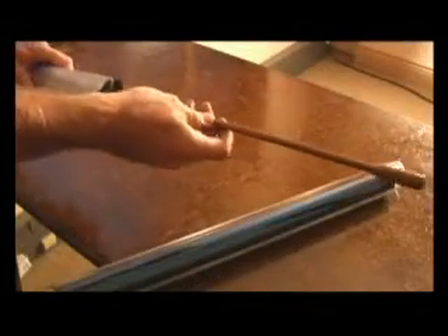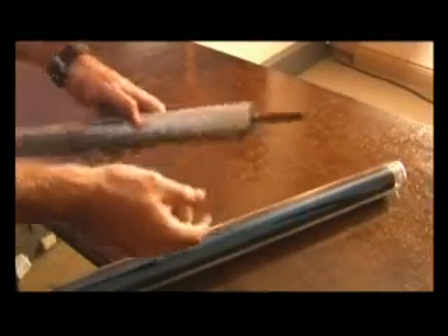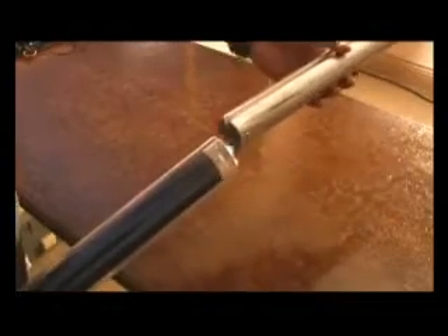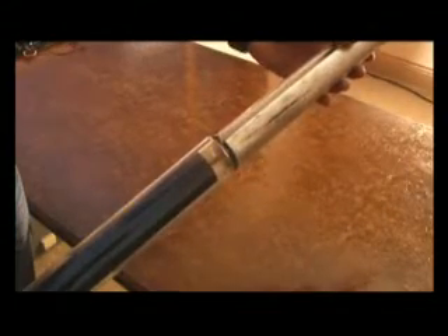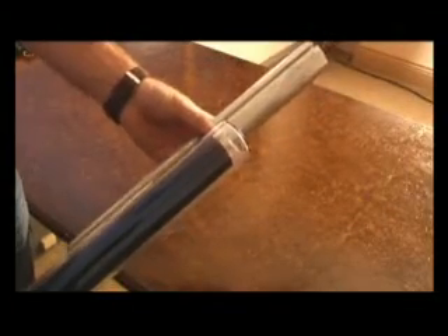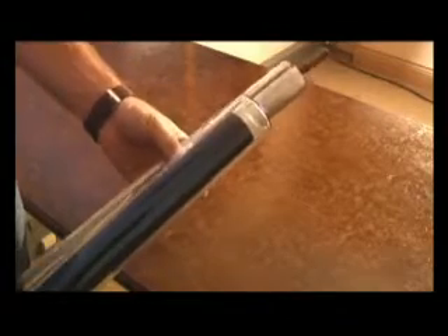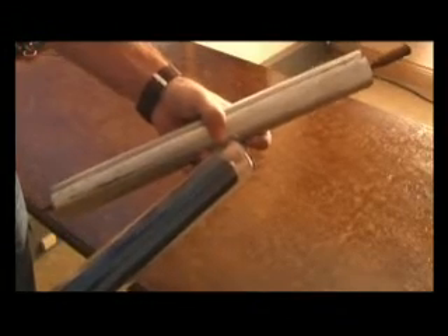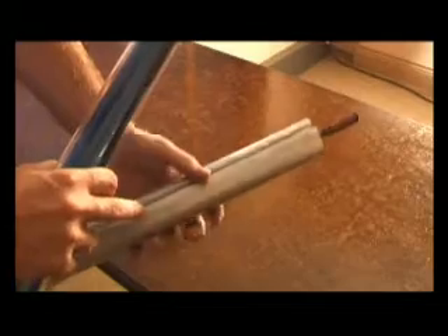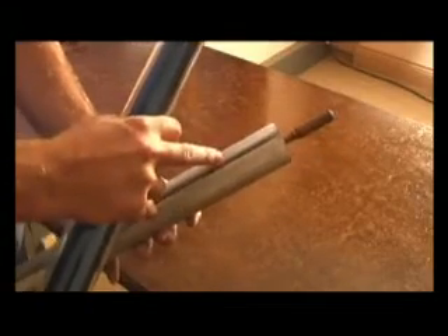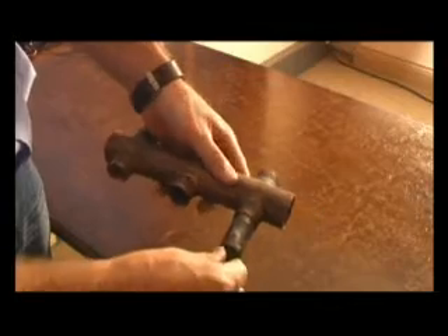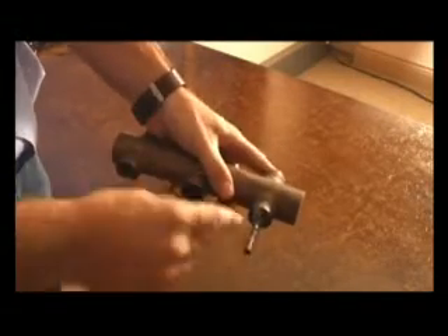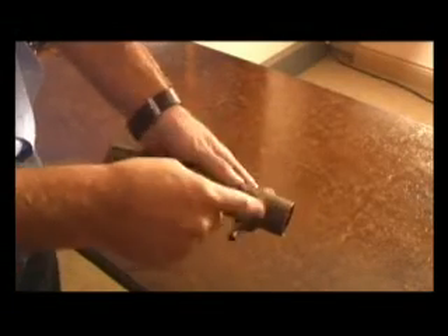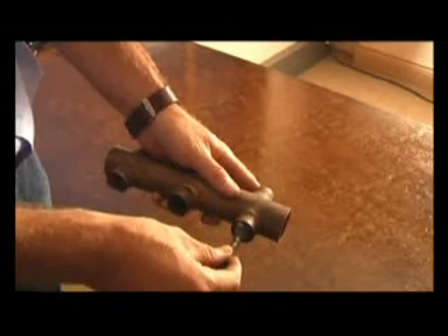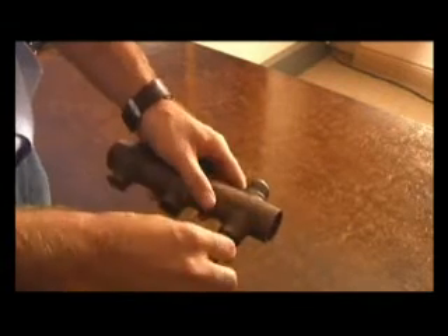Another type of heat pipe would be in the double glass type heat pipe. The tube takes the heat pipe on the inside on an aluminium fin, which transfers the heat from the inside of the tube or the evacuated tube onto the aluminium fin and then onto the heat pipe. The heat pipe's probe is plugged into a manifold such as this one. It's imperative to have a very good seal between the probe or the bulb and the manifold itself.